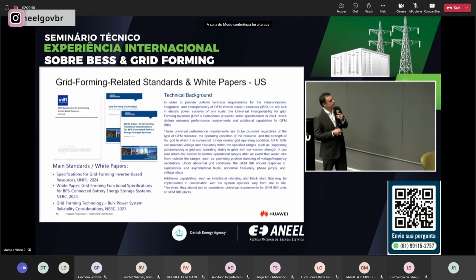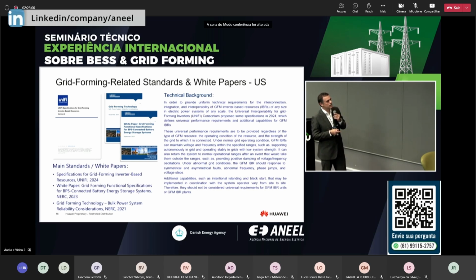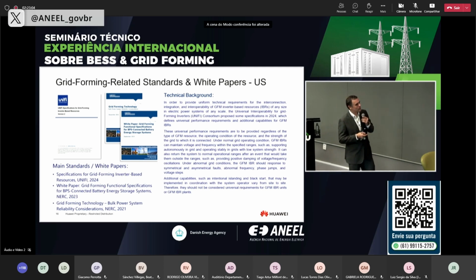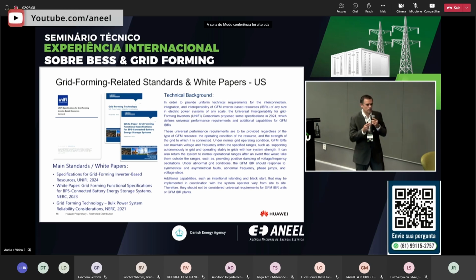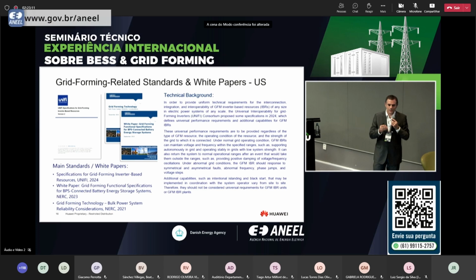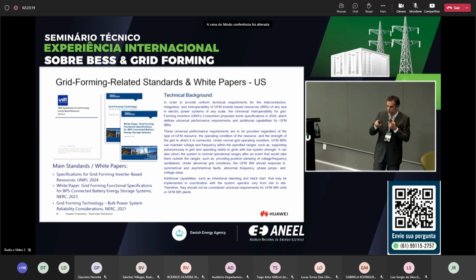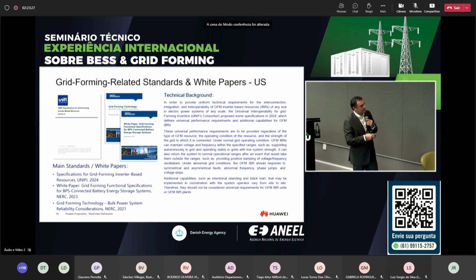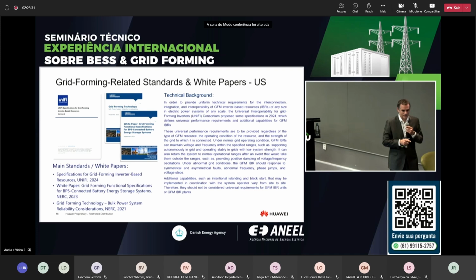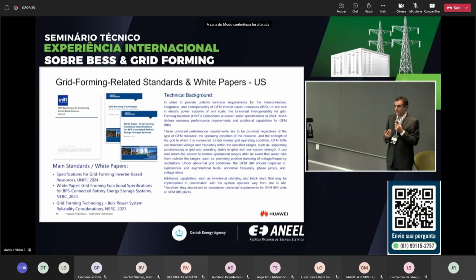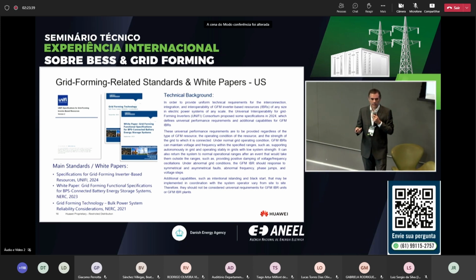We can take a very quick overview about the US. One interesting point about US is that we need to provide a grid forming solution thinking like a synchronous generator, like a voltage source with impedance. So if there is no synchronous generator, the system will still keep working. But this topic about islanding and black start is very important, because islanding is related to safety of the grid. Can we deploy an islanding-ready solution anywhere? No - this should be discussed with the system operator to think very clearly about where the system that can run an island will be, because it's very related to safety.